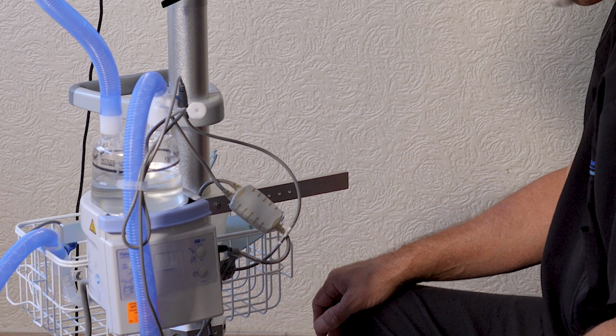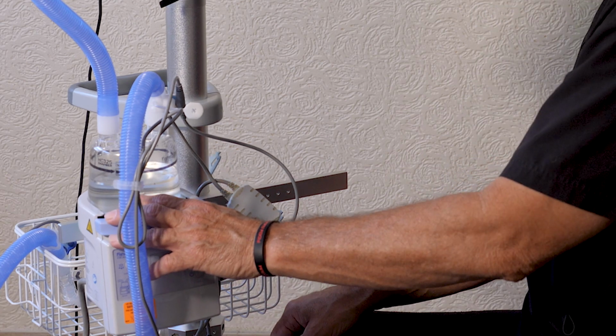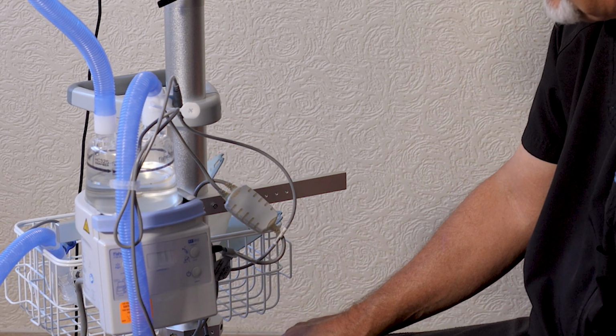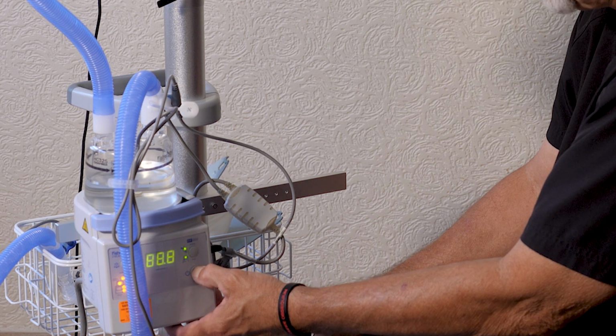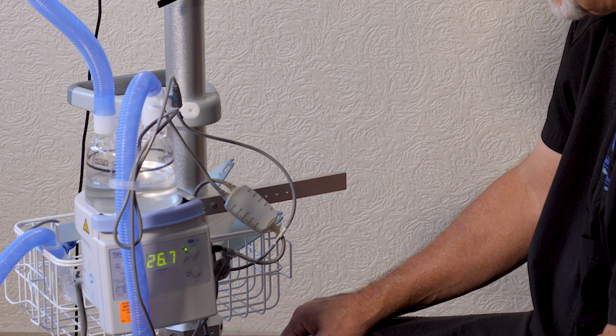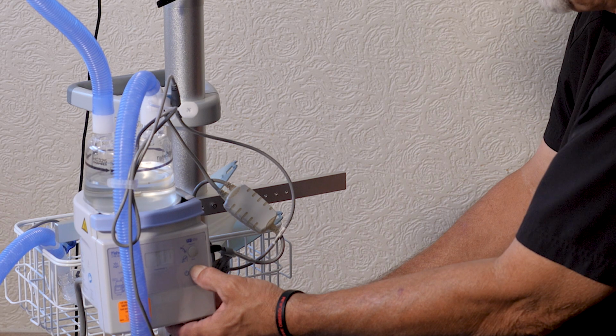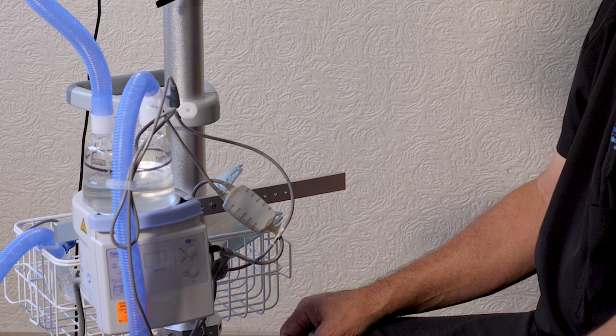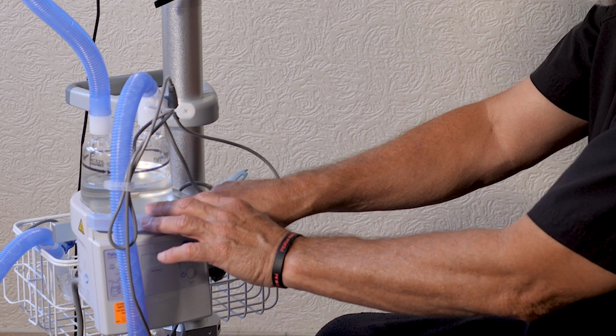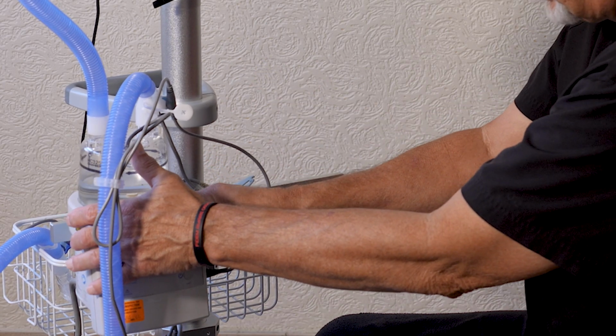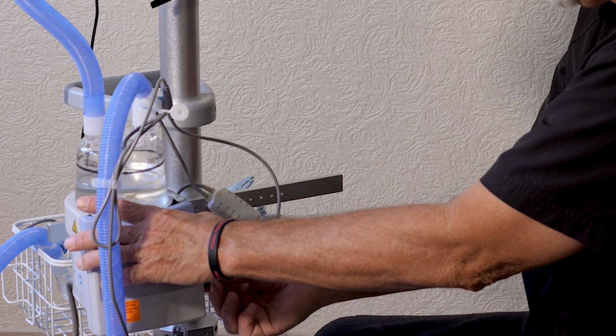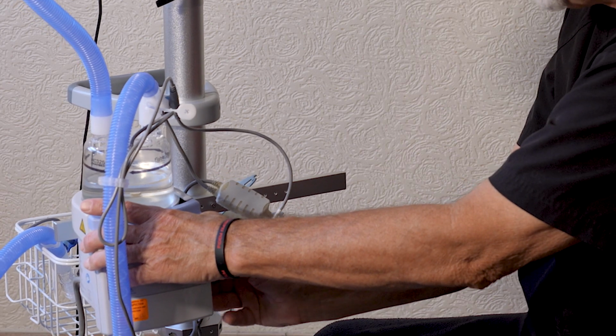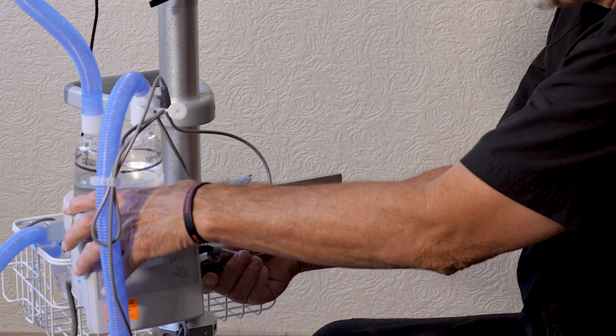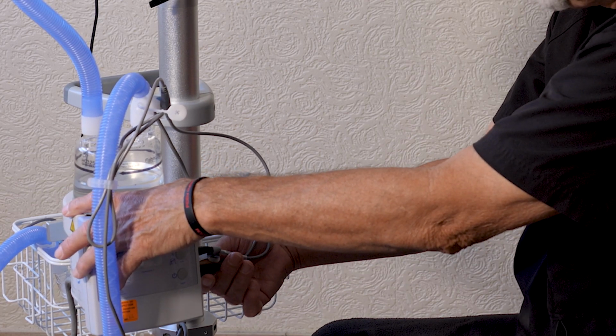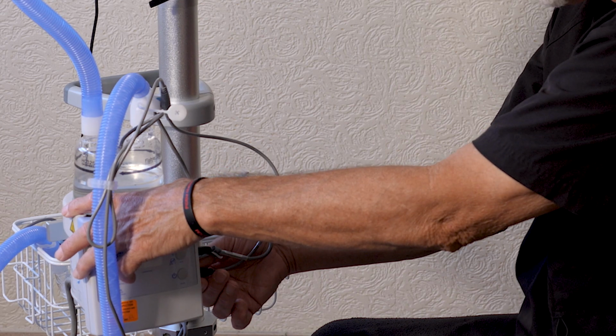So if your water chamber is full, then the next thing you want to do with the humidifier is turn it off. Right now it is off, but just to illustrate, turning it on is this button here, and then turning it back off is right here. So you turn it off, and then the next thing you want to do is remove the heater wire cable and put it back. You want to remove the temperature probe cable and put it back. And by the way, when you're putting these in, make sure that they slide in easy. If it doesn't slide in easy, don't force it. We've had a lot of people break these cables this way. Just slide it till you get to the point where it slides in easy.